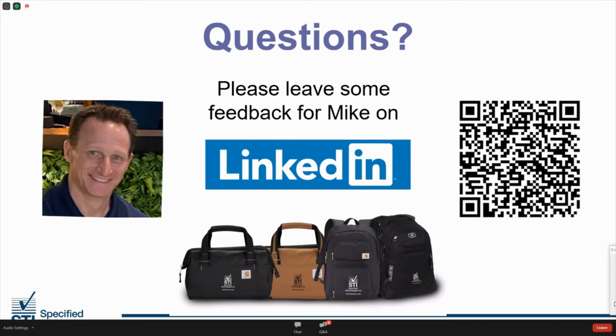So basically you need to have the systems that will support the actual installation on site. You need multiple UL tests or Intertek tests with project data that will support the writing of the judgment. And then that is generally submitted to the architect or the owners, or in some states, for example Mecklenburg County in North Carolina and San Francisco in California, those areas often require a third-party engineering stamp or review. That's generally provided separately from the manufacturers through third-party engineering firms, because people don't want the foxes watching the henhouse.